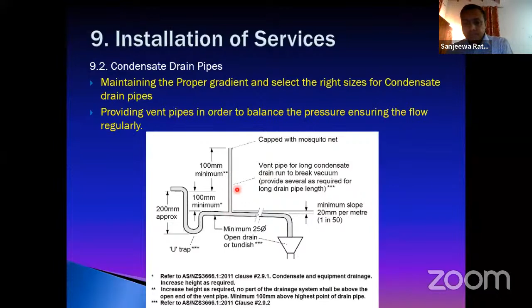And sometimes if the drain line is too long, with the span of the project, frequently the contractor must put a vent pipe in order to balance the pressure. Otherwise, even though the drain line is properly sized, the water flow will not happen properly if the pressure is not balanced. So it is an important practice when the drain network is very long. In a few places we have to put this vent pipe.